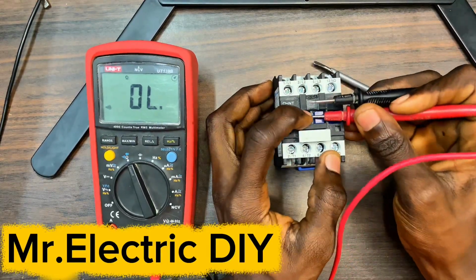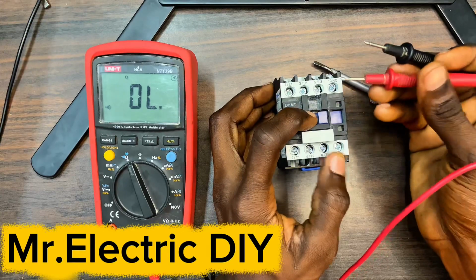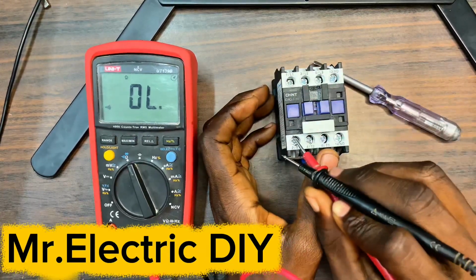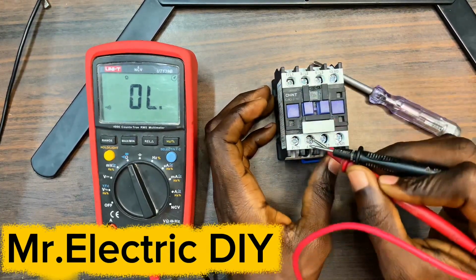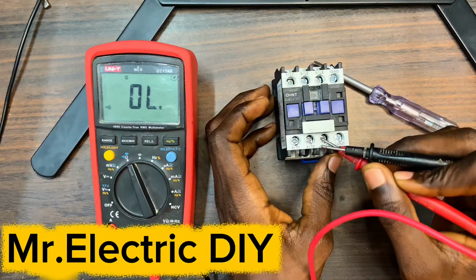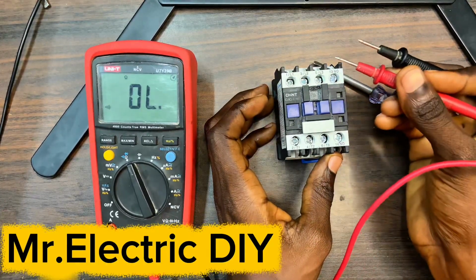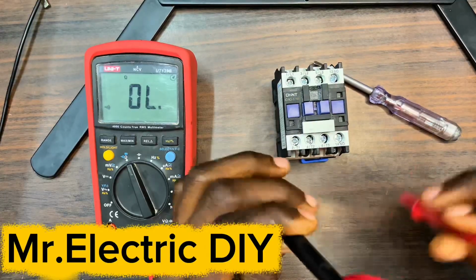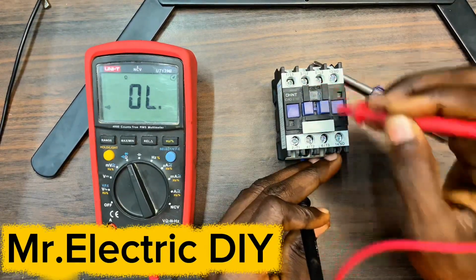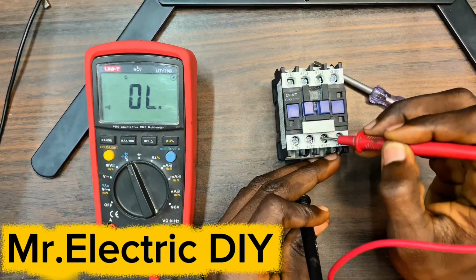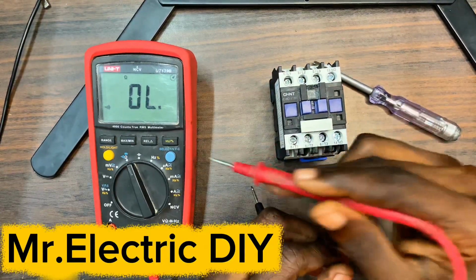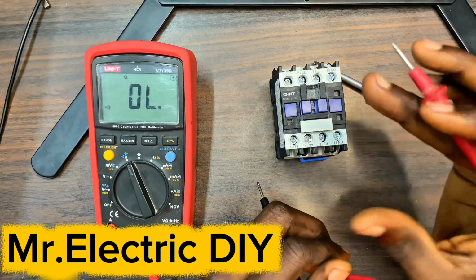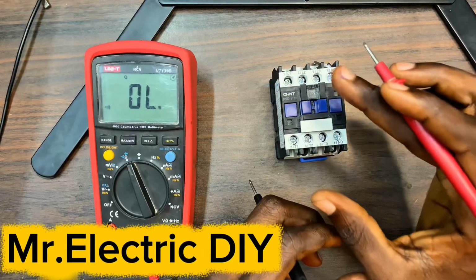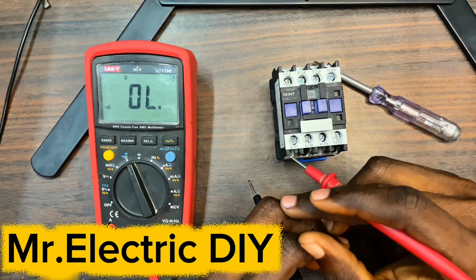When it's energized, there's going to be a flow of current from this side to this side, from here to here, from here to here. If your load is actually a 3-phase load, there's going to be a flow of current from here to here, from here to here, from here to here. So from the readings that the multimeter provided, I can surely say that the power terminals are in good condition.